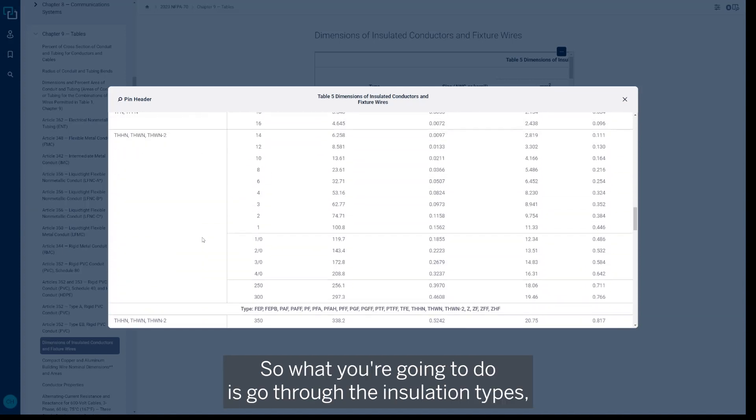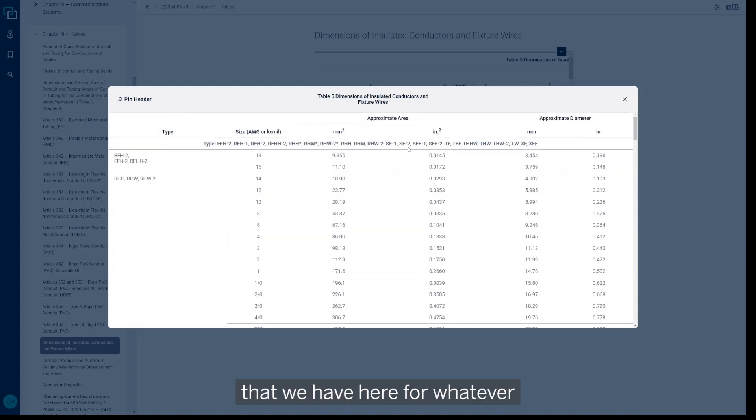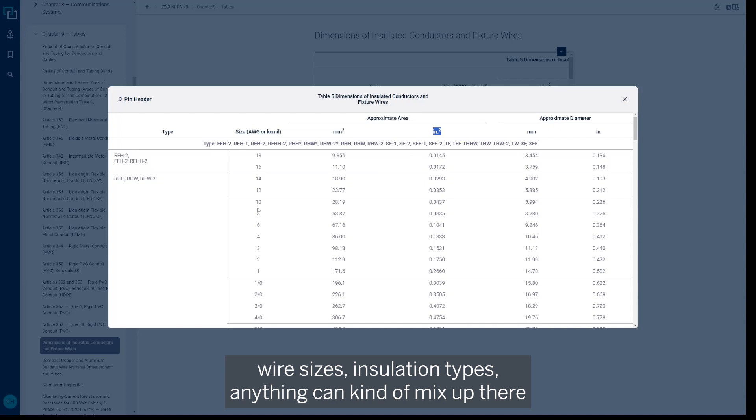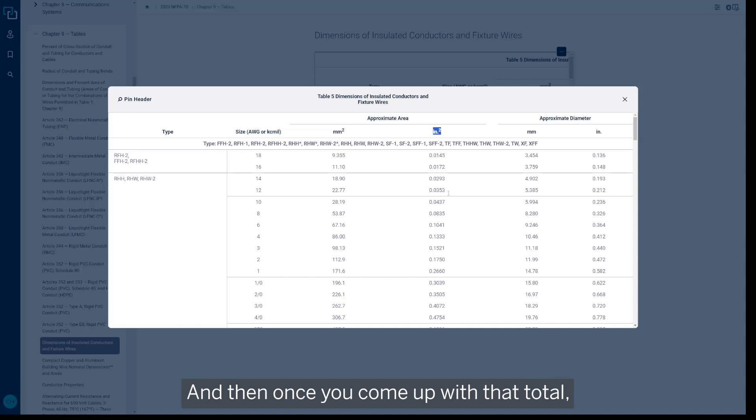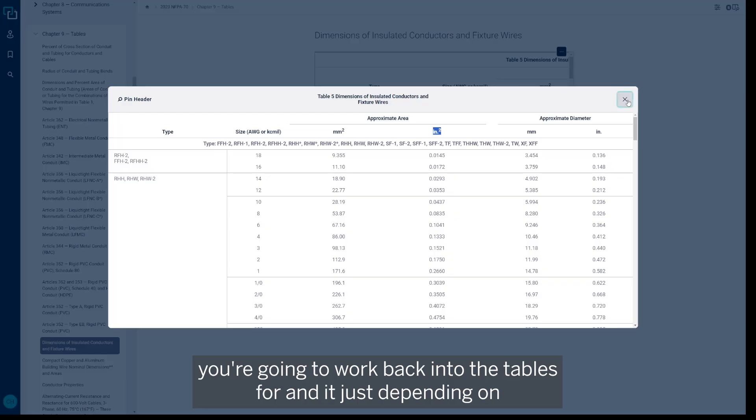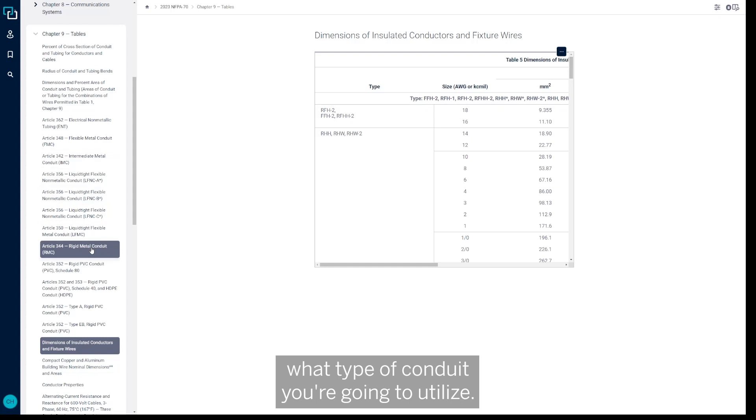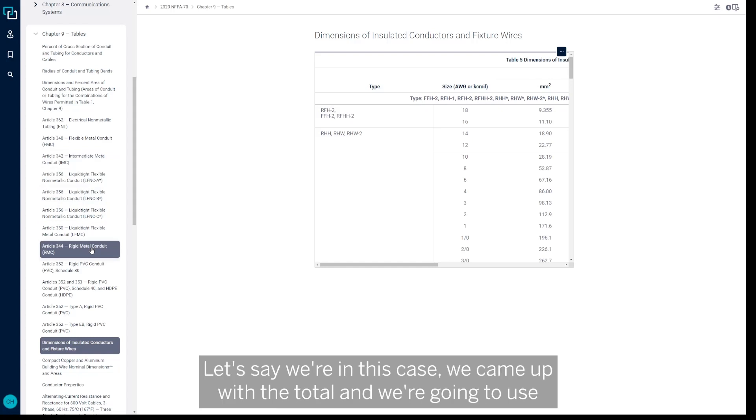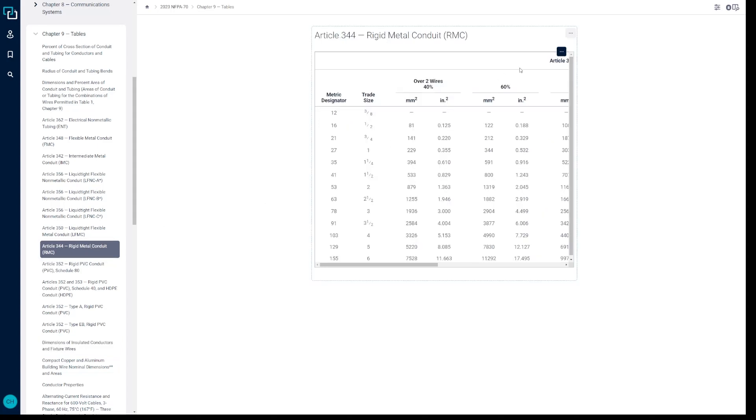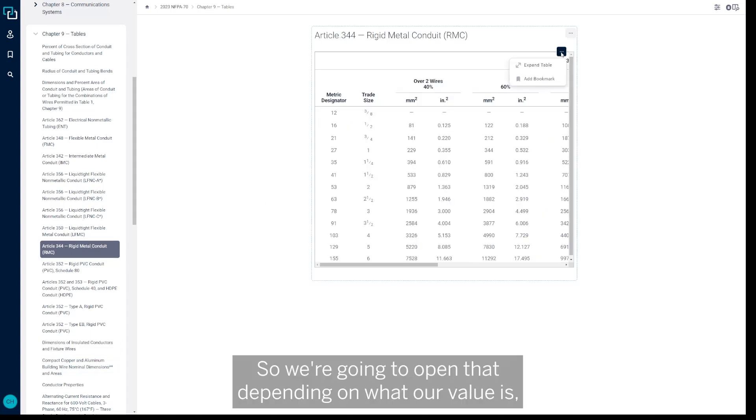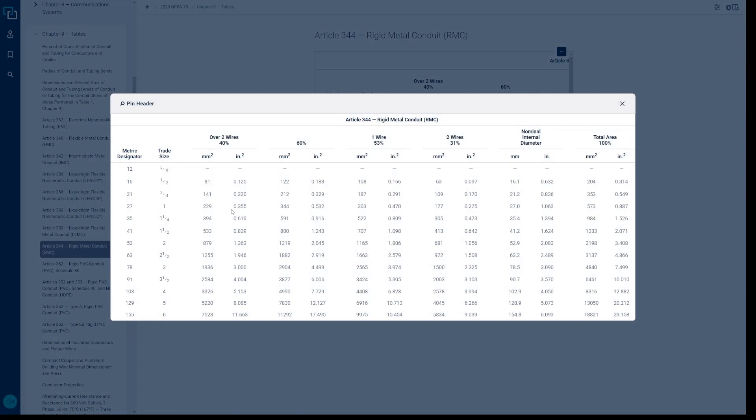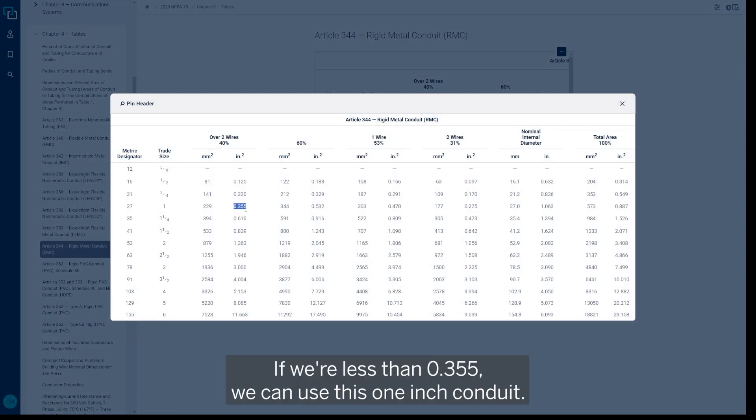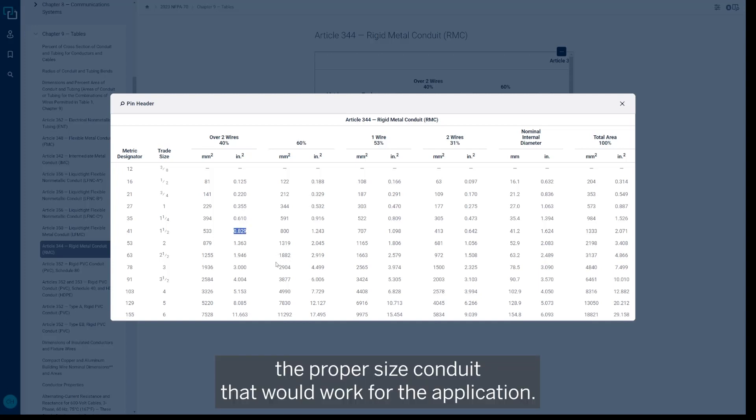in that area and inches squared column that we have here for whatever wire sizes, insulation types—anything can kind of mix up there—and then you can come up with a total. And then once you come up with that total, you're going to work back into the Table 4. And depending on what type of conduit you're going to utilize—let's say in this case we came up with a total and we're going to use a rigid metal conduit or type RMC instead of EMT now—so we're going to open that. Depending on what our value is, we're going to pick the proper size conduit. If we're less than 0.355, we can use this one inch conduit. If we go over that number, we would have to keep climbing up until we get to the proper size conduit that would work for the application.